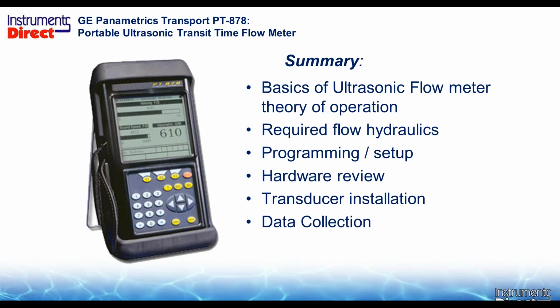So what did we learn today? This is a tool, a very popular method of technology, with which you can do discovery, flow surveys, and dedicated flow monitoring. We learned about the theory of operation and where this type of technology works. Basically any aqueous application that is ultra clean, up to chunks of stuff, is designed to work with an ultrasonic transit time flow meter. Get some straight run of pipe if you have the choice. If you don't, the best thing you can do is go downstream two-thirds of the available footprint and try it there. There may be some applications where you will not get a reading because you don't have enough straight run of pipe. The meter will fault out and you'll get no data. But bad data is just as bad, so you'd rather have no data than bad data.